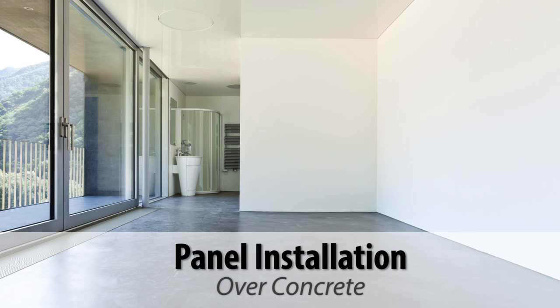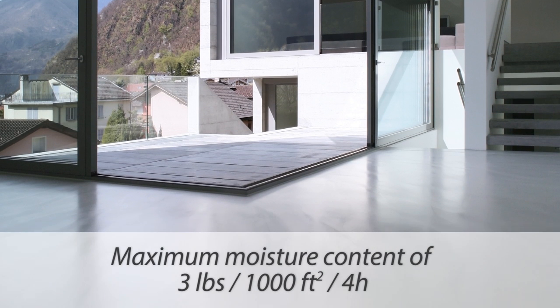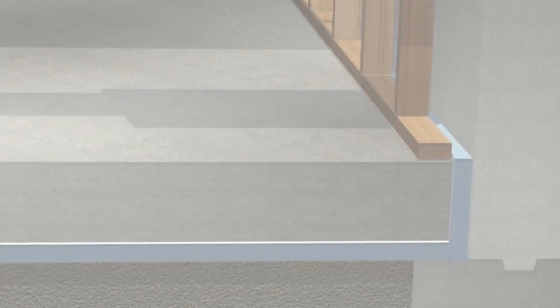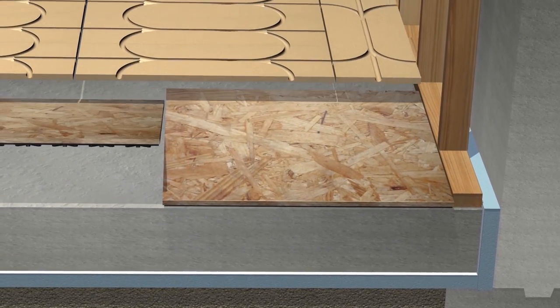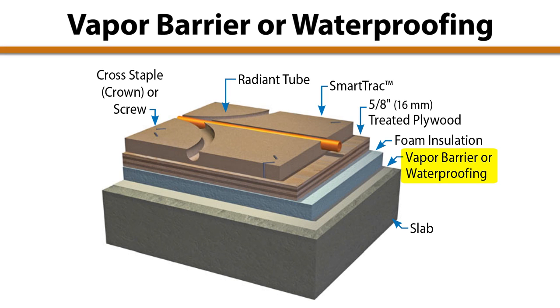SmartTrac can also be installed over fully cured concrete with extra attention to moisture control. Newly poured concrete should have a minimum of 60 days curing time. The maximum acceptable reading with a calcium chloride test is 3 pounds of moisture emitted per 1,000 square feet over 4 hours. To reduce heat loss, under-slab and perimeter insulation is recommended. In new construction, foam insulation is commonly installed under the concrete slab. For retrofit installations, materials such as dry core or barricade can act as a moisture barrier, thermal break, and insulator. A vapor barrier or water sealant over the concrete will help prevent groundwater damage to the SmartTrac panels and flooring. Refer to the SmartTrac manual for more details about over-concrete installation.